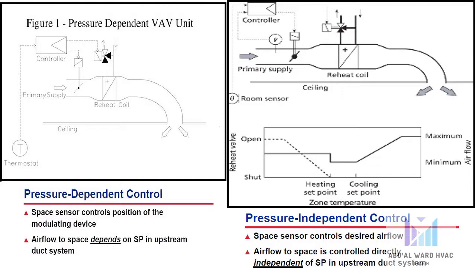In contrast, a pressure independent VAV control scheme directly controls the actual volume of primary air that flows to the space. An airflow measuring device on the terminal unit makes this possible. The position of the modulation device is not directly controlled — it is basically a byproduct of regulating the airflow through the unit. Because the airflow delivered to the space is directly controlled, it is independent of inlet static pressure. Pressure independent control increases the stability of airflow control and allows minimum and maximum airflow settings to become actual airflow values rather than physical positions of the modulation device. It is clearly the most popular form of VAV terminal unit control.